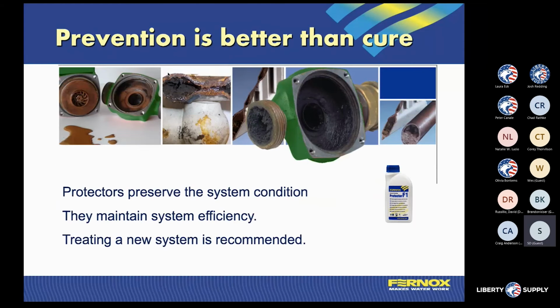So we want to talk about creating a cure. How do we create that cure? We're going to talk about the prevention that our product can make. The one thing I'll mention at this point is that anytime we start with a system that has not been cleaned and flushed and dealt with, if we start putting inhibitors in that system, it's not going to clean the system out. It's just going to stop the system from getting worse. At the end of the day, we still need to find devices or ways to either flush or remove the particulates and the pollutants out of that system.